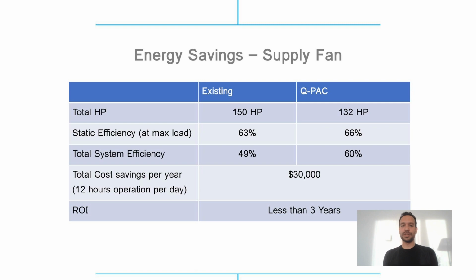Static efficiency, this was a fairly efficient fan. The existing fan was 63%. As I said, it was a backward curve SWSI fan wheel, and that went up to 66%, the static efficiency just on the air. But the big difference came from just the motor size. So the current efficiency was below 50% on their system. That went up to about 60%.